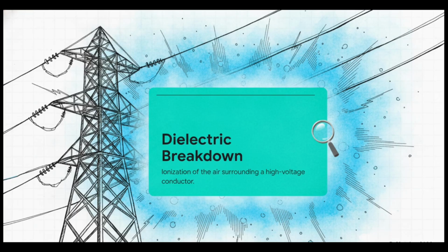Okay, to understand that weird blue glow and the hissing sound, we have to look at the physics of the air itself. It all comes down to dielectric breakdown. This is basically a localized electrical breakdown, or ionization, of the air surrounding a high-voltage conductor. See, under normal conditions, the air around us is an excellent insulator. It keeps the electricity safely inside the wire where it belongs. But when you raise the alternating voltage on a transmission line, the electric field, the potential gradient right at the surface of that conductor, shoots way up. If that electric field gets intense enough, it can literally overwhelm the insulating properties of the air. It ionizes the air molecules, and suddenly the air itself becomes conductive.